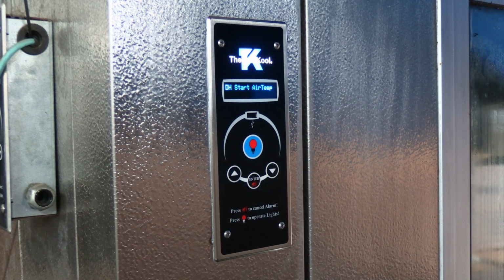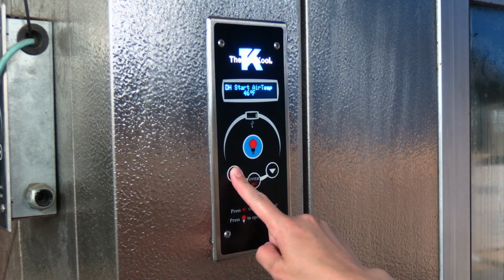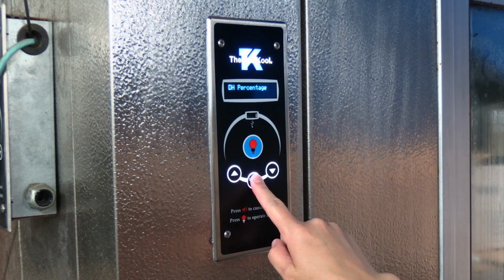This option allows you to select the threshold temperature for your door heater, meaning, if 45 degrees Fahrenheit is entered, the door heater will start if the temperature is 45 degrees Fahrenheit or below. The default range is from 0 to 150 degrees Fahrenheit. To change the temperature, press the up or down arrow, then press Enter.